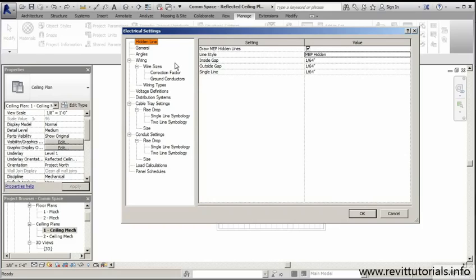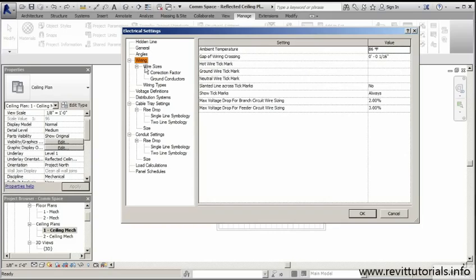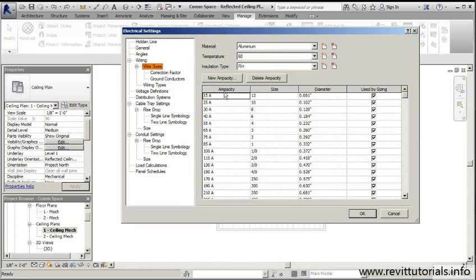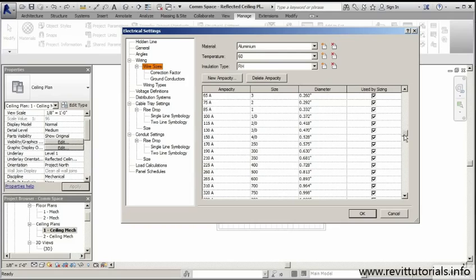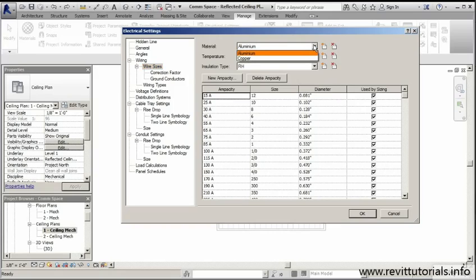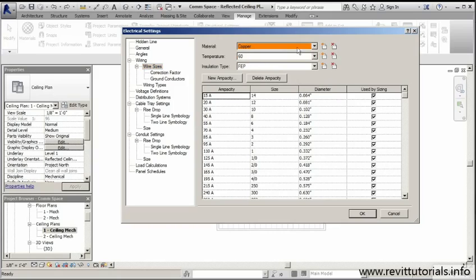The first thing I'd like to jump to is our wiring. Under wiring here, we can tell Revit a number of parameters associated with our wire. We can work with wire size. You'll see from this window we've got a number of wire sizes to choose from. It tells us our ampacity, wire size, and diameter. You can scroll down and see we have a lot to work with here. Not only do we have information here, but if you go to the top under material, we have the option to choose the type of material for our wiring. We can go with aluminum or copper. In our system, we're going to have copper wiring, so I'll switch from aluminum to copper.